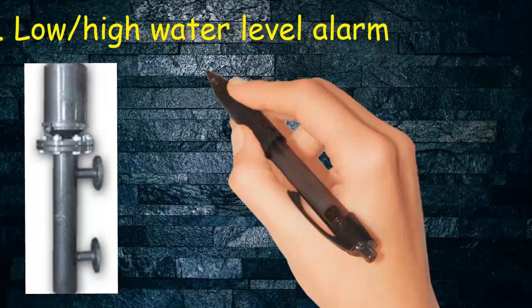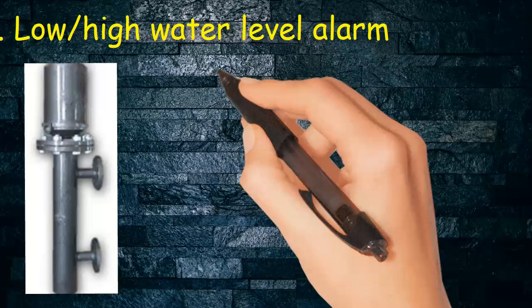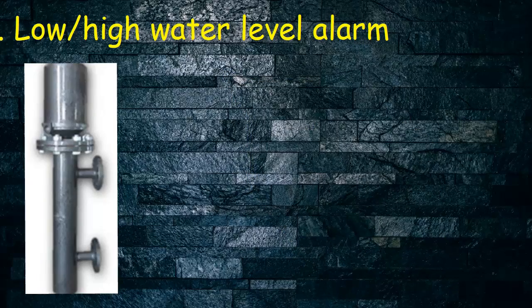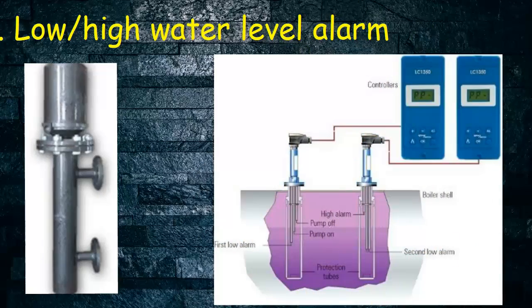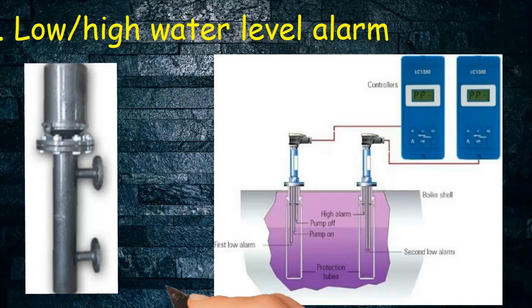Whereas low or no water level in the drum will lead to overheating of tubes and can lead to fire or meltdown of the complete boiler. The low high water level alarm provides an early warning to the operator for taking appropriate action to manage the water level inside the boiler water drum.